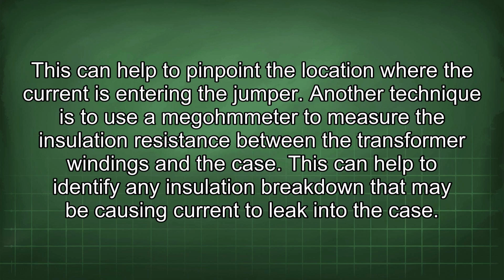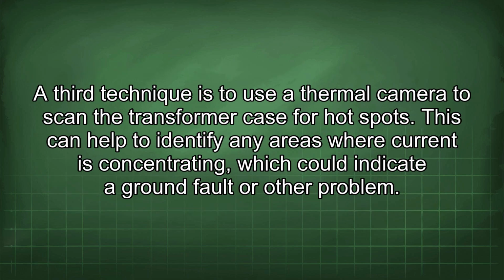Another technique is to use a megohmmeter to measure the insulation resistance between the transformer windings and the case. This can help to identify any insulation breakdown that may be causing current to leak into the case. A third technique is to use a thermal camera to scan the transformer case for hot spots. This can help to identify any areas where current is concentrating, which could indicate a ground fault or other problem.